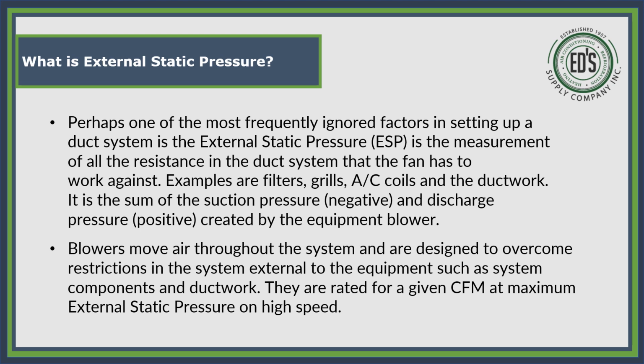So as the blower motor pushes air out, it has to suck air in to be able to push it out. It can only push out what it's taking in. So you've got to understand these units do not make air, they're moving it. Blowers move air throughout the system and are designed to overcome restrictions in the system external to the equipment, such as system components and ductwork. They are rated for a given CFM at maximum external static pressure on high speed.